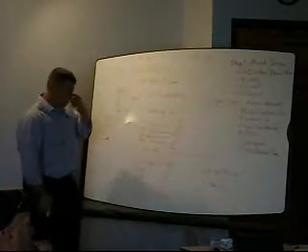So we went through all the fittings, all the travel distance, to come up with a total equivalent pipe length. We take it to the table, we know our flow rate, and we determine how much head. This is feet of head. Make sense? How much force do I have to deliver to get that water there? We figured out one part of the TDH.